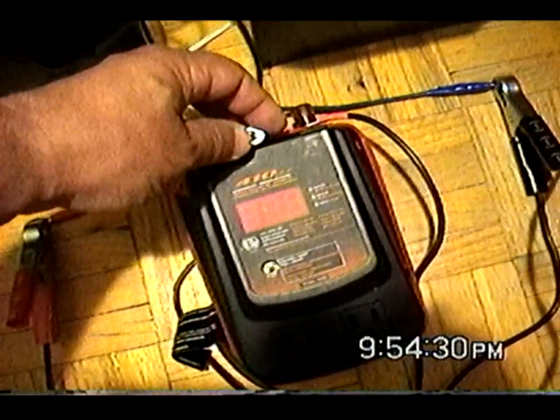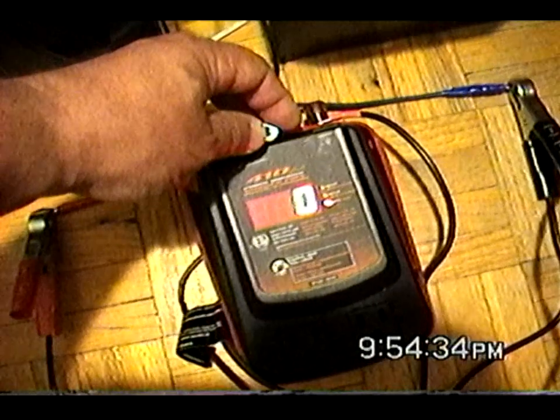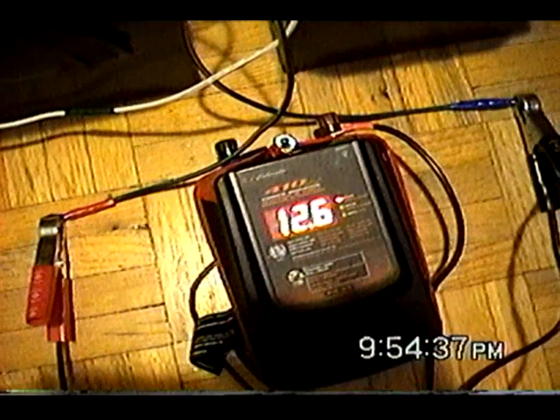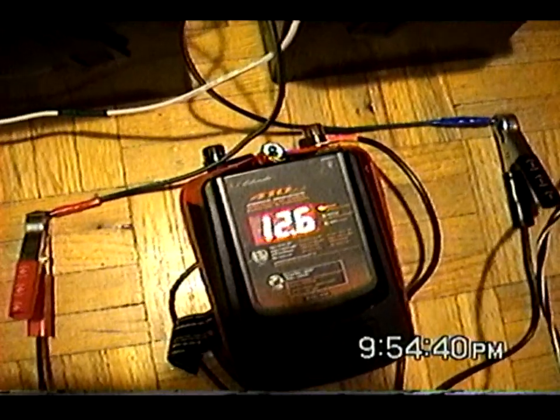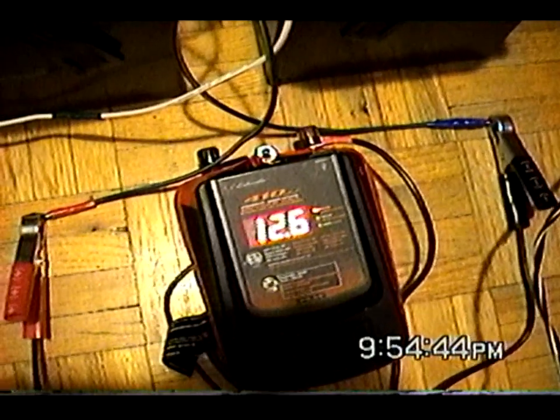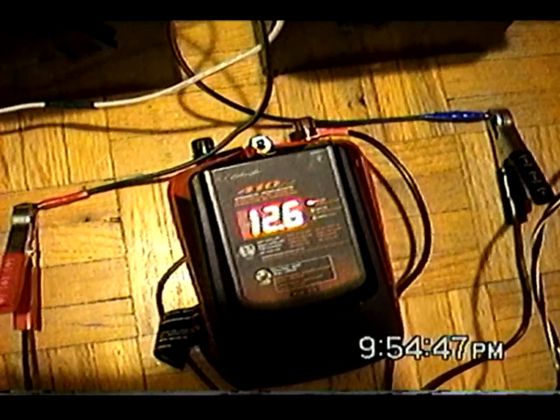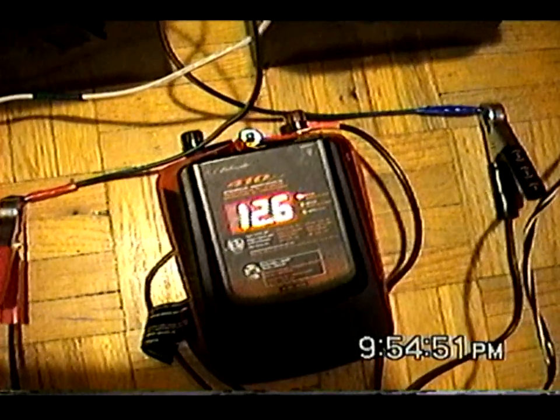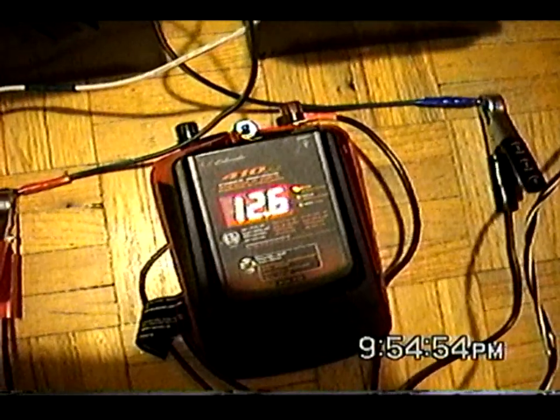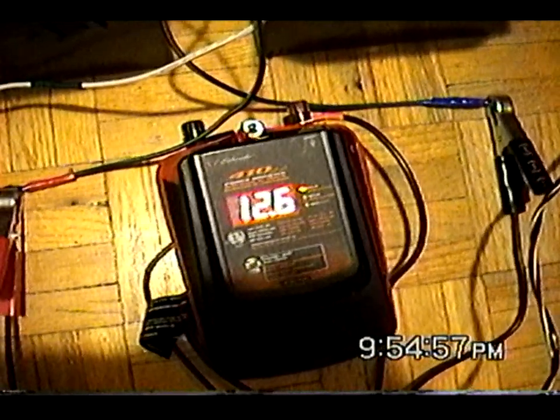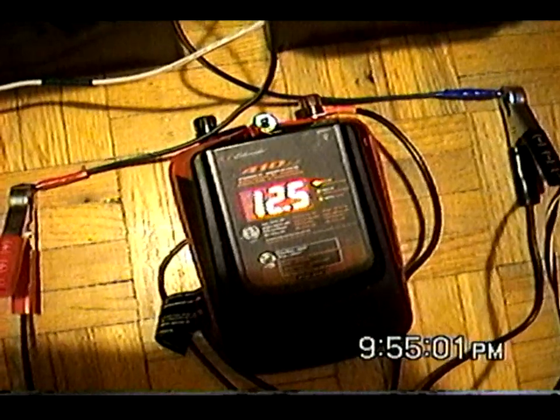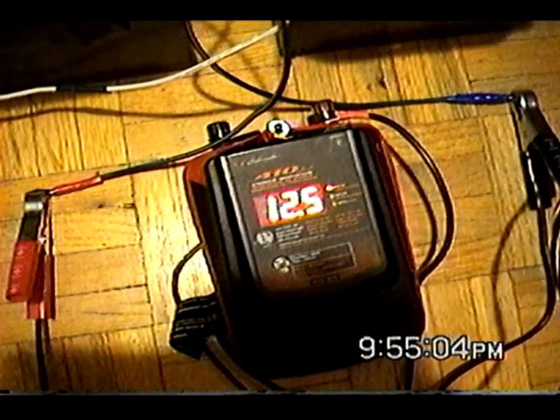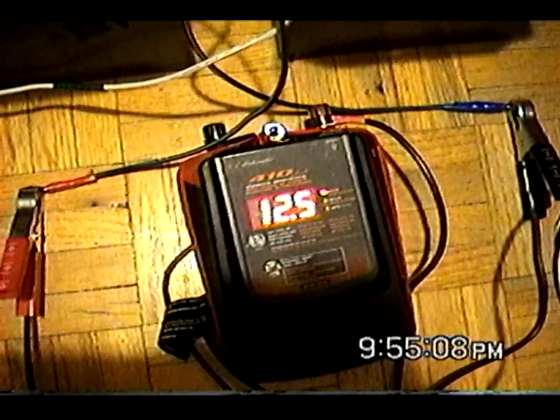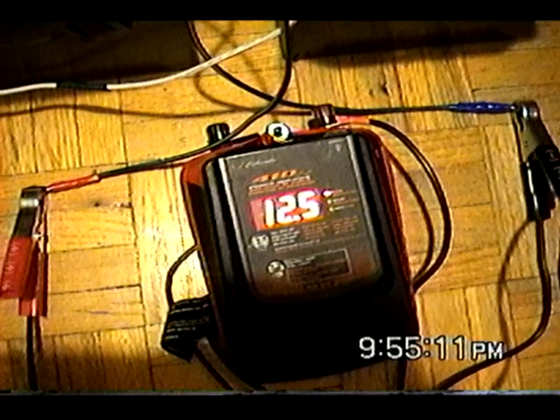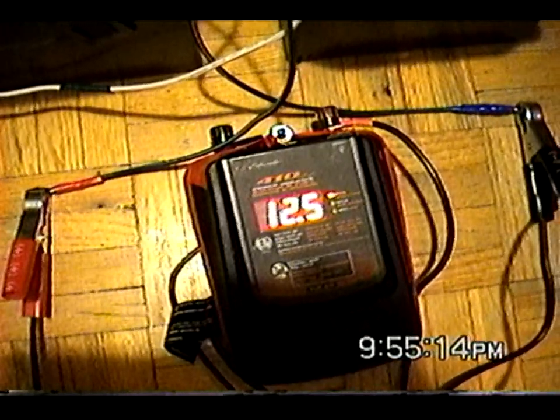Now what happened is that the Tesla switch switched and the machine just shut down. There was 12.4, now it's 12.6 volts, because the batteries are a bit different. Right now they are producing a bit different voltage, but with time everything should come to an equilibrium. To avoid that, as you can see, sometimes some inverters could just shut down during the switches because the relays are disconnecting the contacts momentarily.